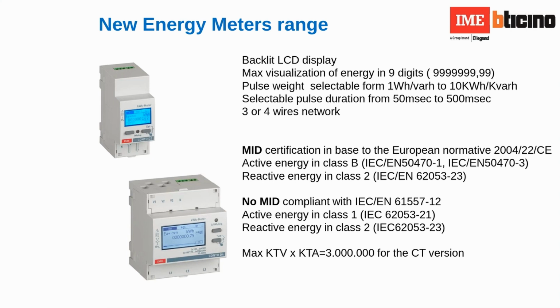The standard EN 61557 specifies the requirements for power metering that measure and monitor the electrical quantities within an electrical distribution system, and defines the performance in single and three-phase system up to 1000 volt. So we can say this for the low voltage. This standard classifies the different electrical parameters in several classes, like the precision class 0.5, 1, or 3. It's important to say that energy meters with an external current transformer, so indirect energy meters, can be also used for medium voltage.